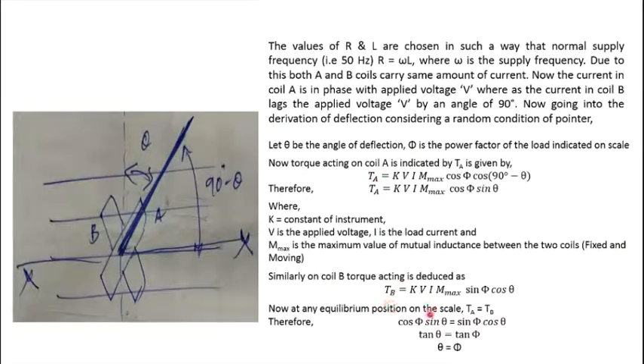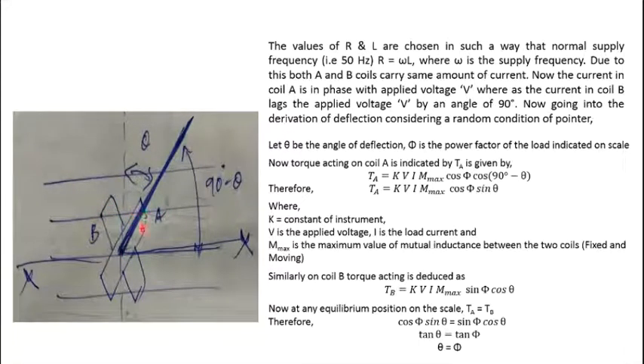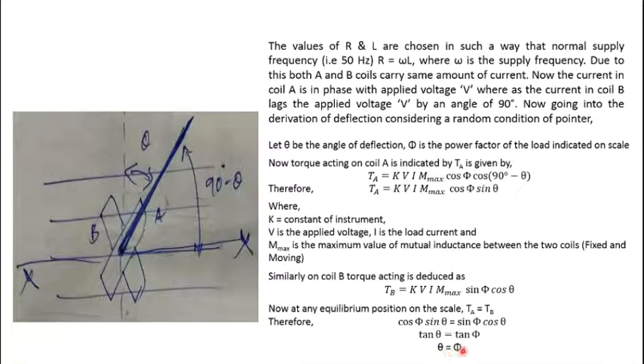Similarly, torque B equals k × V × I × M_max × sin(φ) × cos(θ). At equilibrium, when the pointer is at rest, torque A equals torque B. Since the common quantities k, V, I, and M_max cancel out, we get cos(φ) × sin(θ) = sin(φ) × cos(θ), which means tan(θ) = tan(φ), therefore θ = φ. This is a very important equation showing that the deflection angle is equal to the phase displacement angle between voltage and current.